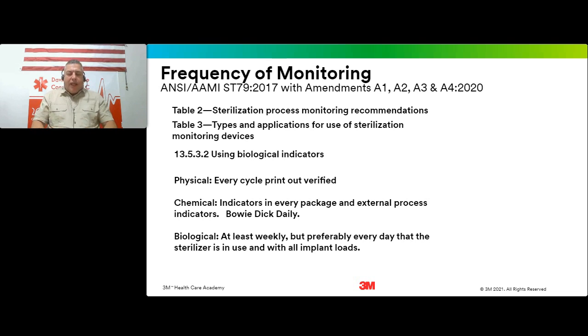Biological. Okay, we'll get into this in a little more detail coming up. Your biological should be at least weekly, but preferably every day. This is language right out of the document - every day that the sterilizer is in use and with implant loads. I want to give you a heads up that the accreditation agencies, and even some Department of Public Health inspections, don't look at that word 'preferably' lightly. They really emphasize the every day, okay?